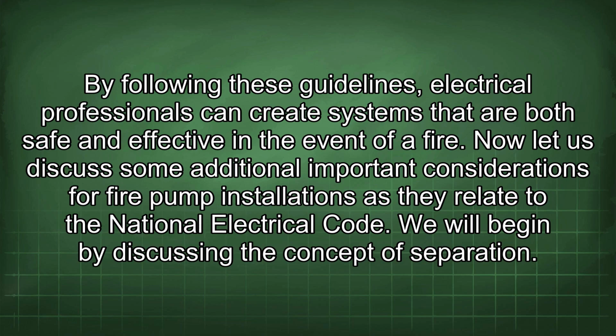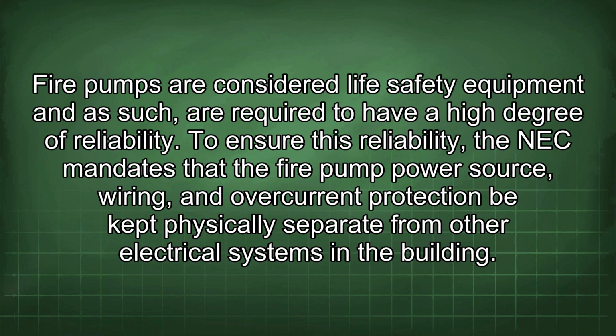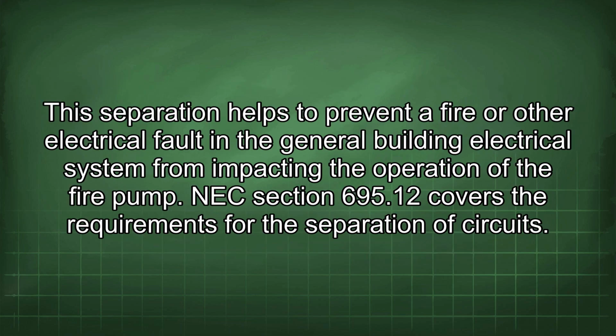We will begin by discussing the concept of separation. Fire pumps are considered life safety equipment and, as such, are required to have a high degree of reliability. To ensure this reliability, the NEC mandates that the fire pump power source, wiring, and overcurrent protection be kept physically separate from other electrical systems in the building. This separation helps to prevent a fire or other electrical fault in the general building electrical system from impacting the operation of the fire pump.